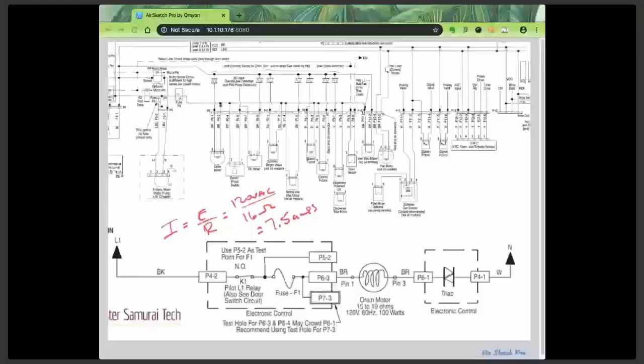Your meter's just using a dinky little 9-volt battery, and it's just measuring normal resistance. It's not measuring reactance, which is the other, larger component of opposition to current flow in the case of a motor. So how then do we calculate amp draw? Again, you use watts, especially when you're dealing with motors. Motors are called non-ohmic. Light bulbs are non-ohmic. So you would use watts.